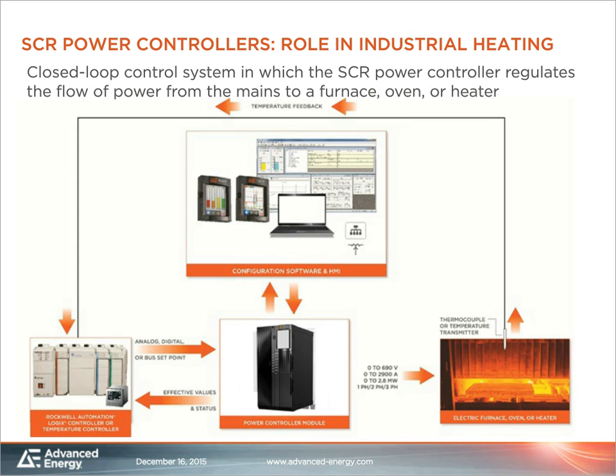Of course, there are also mains voltage variations, and there could be resistance variations for the electrical heating elements in the furnace. These mains voltage variations and resistor variations are normally not regulated by the outer closed loop, but by the power controller itself. That's a way to keep the temperature really stable. Of course, the SCR power controller is a digital unit, so you have all the advantages and possibilities of a digital unit. You can configure it using a PC tool or a little display, and you can do field bus communication.